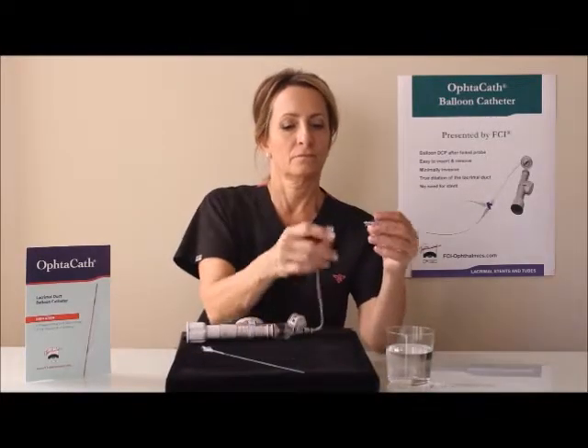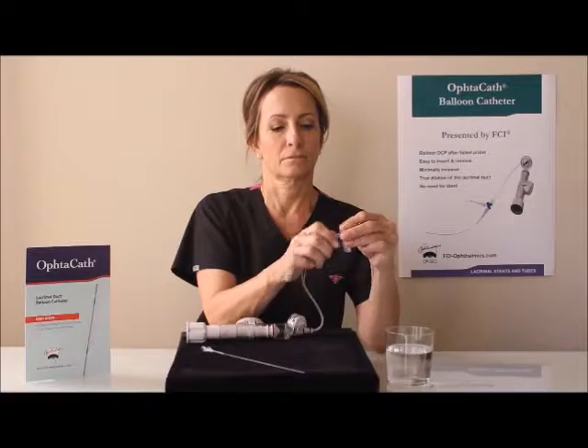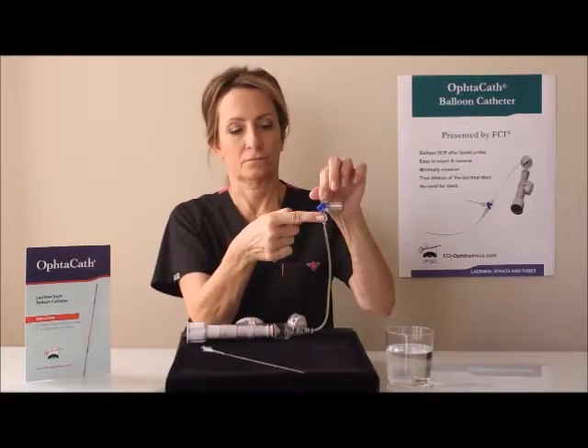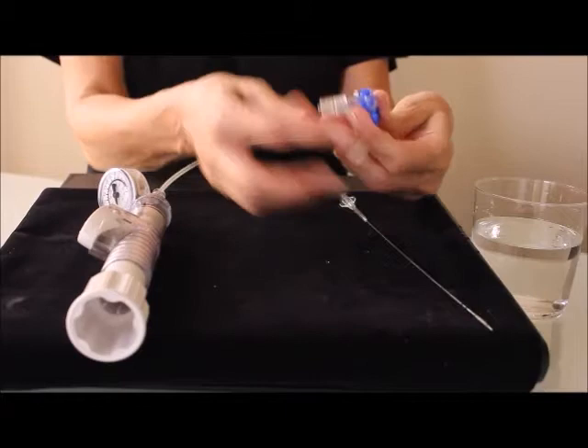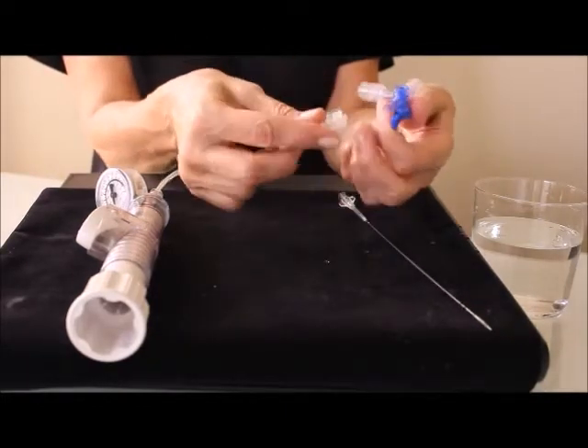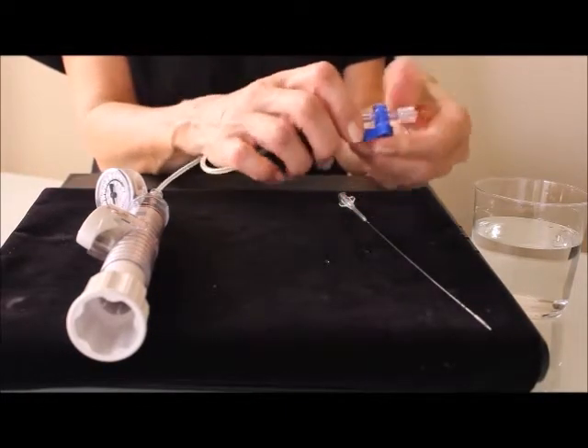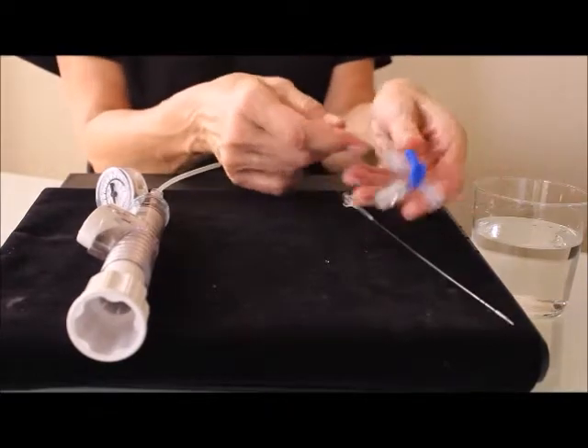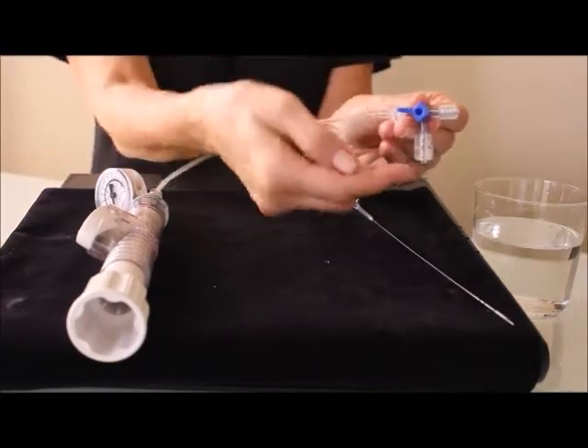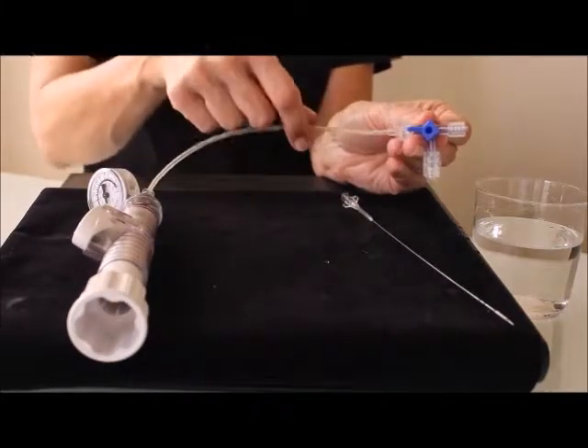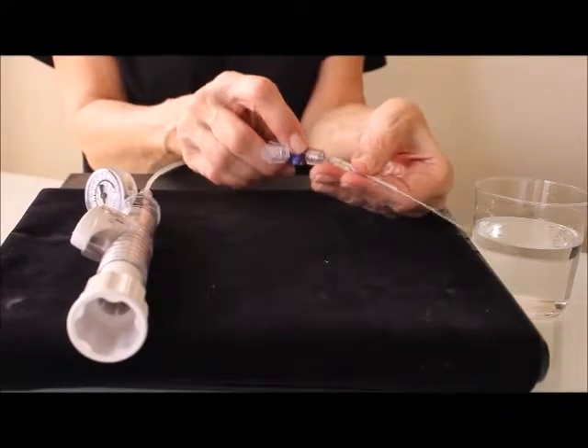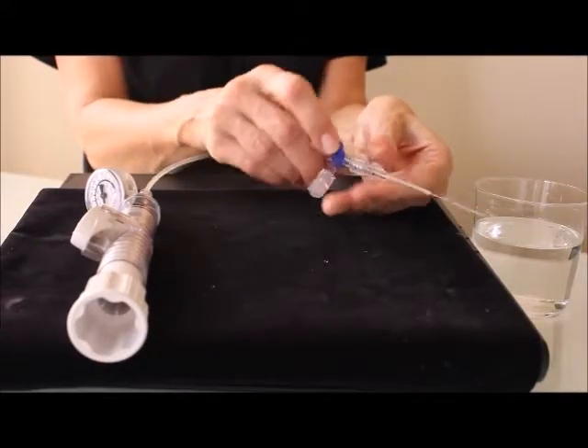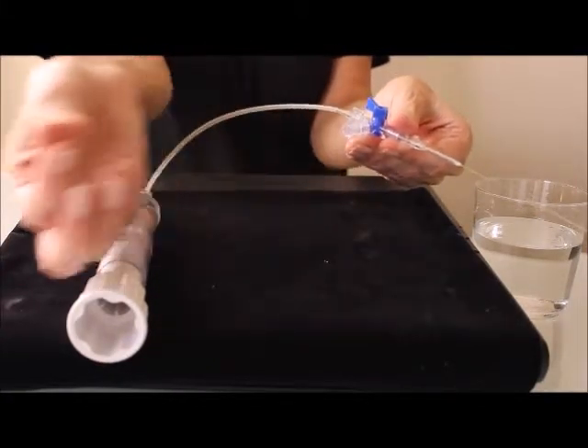If performing a bilateral case, attach the male luer lock of the inflation device to the female end of the 4-way stopcock. Position the stopcock valve lever so that each of the 3 arrows on the blue lever are in front of the 3 connections. Then set aside. Just prior to insertion of the catheter, remove the protective sleeve on the distal end of the balloon and gently lubricate the catheter. It's important to keep that balloon sleeve on the catheter until just prior to use to ensure that nothing on the sterile field can puncture or damage the balloon.